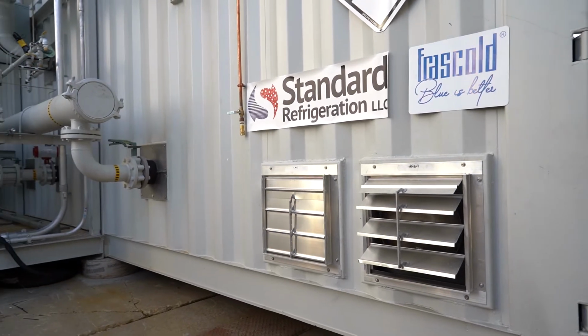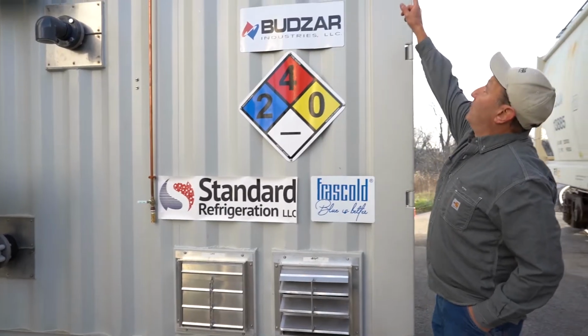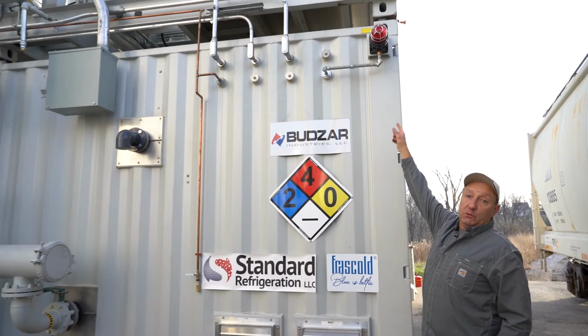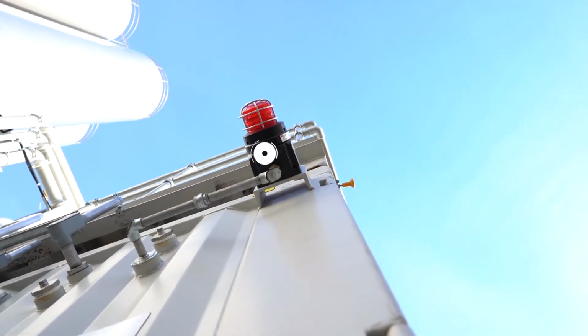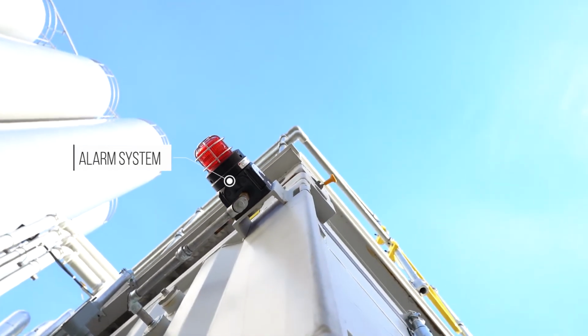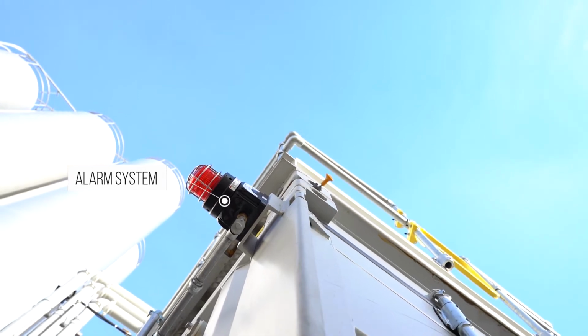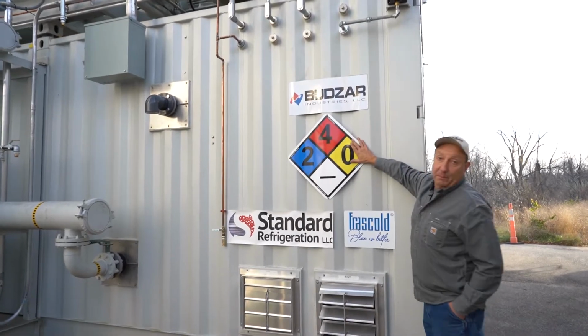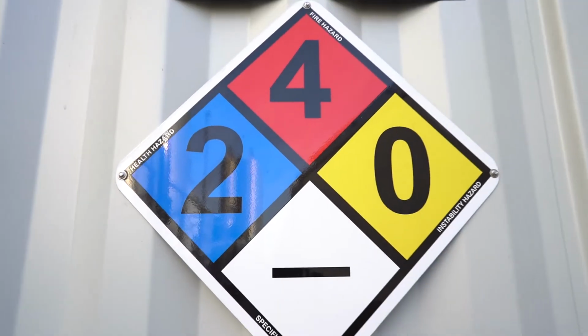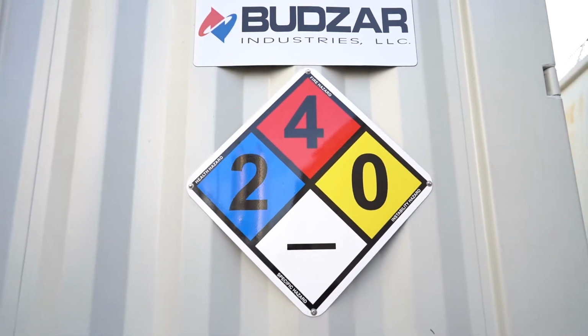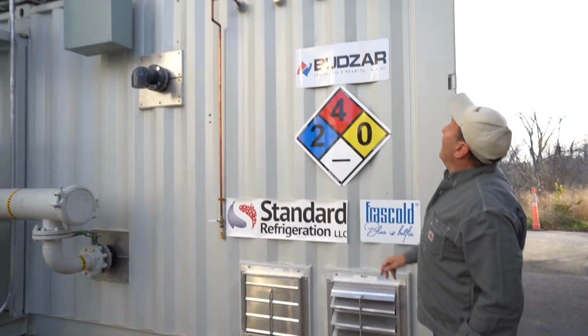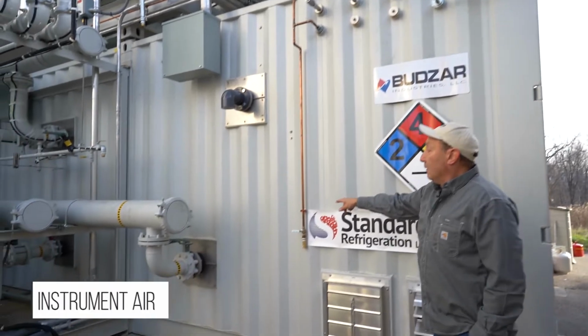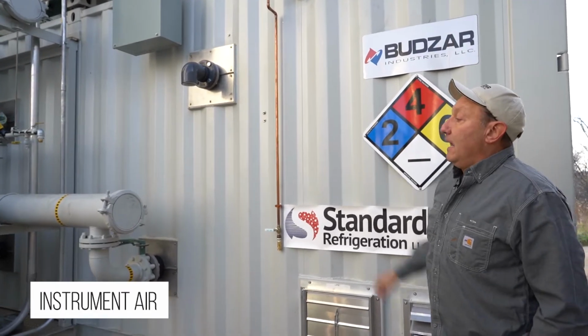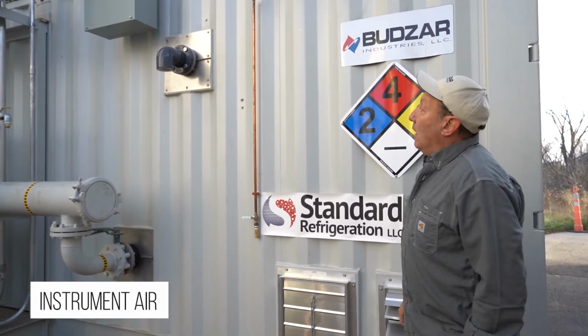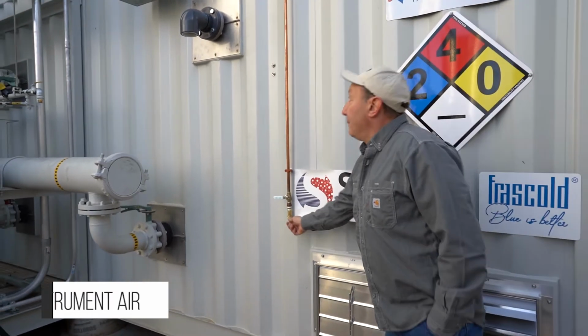The container's temperature controlled. When we get an alarm, we have an audible and visual alarm system. Very obnoxious. You can hear it a mile away. If we have a problem, everybody will know. We have our hazard placard, letting anybody know the hazards involved inside the container. We have instrument air for our pneumatic valves and our purge systems. And we also have a maintenance tap.